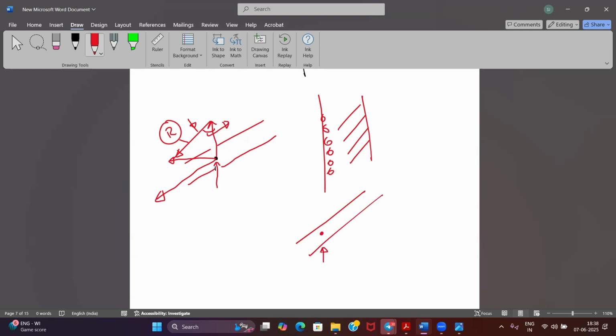This is the throughput, the oil inlet. So this force is acting like this. This is my throughput. There is one centrifugal force which is acting like this. So if I join both, that will be the resultant force. So this angle will depict what angle your purifier plates will be. Is it clear?